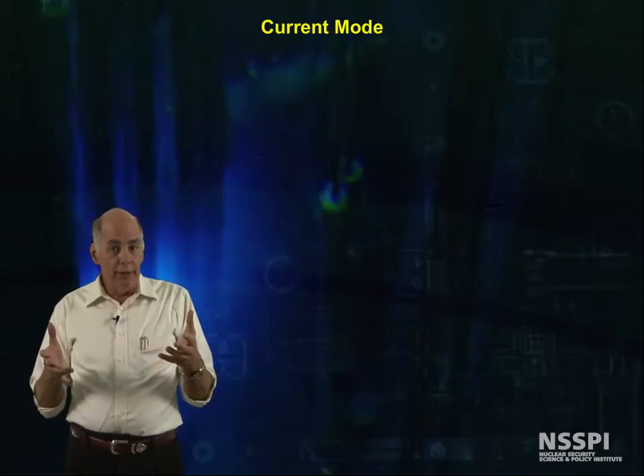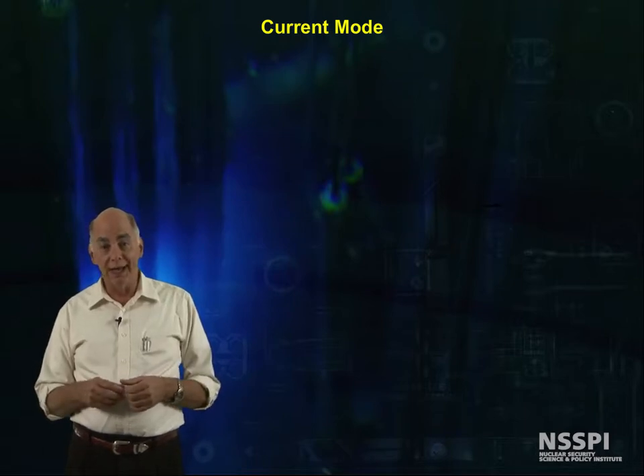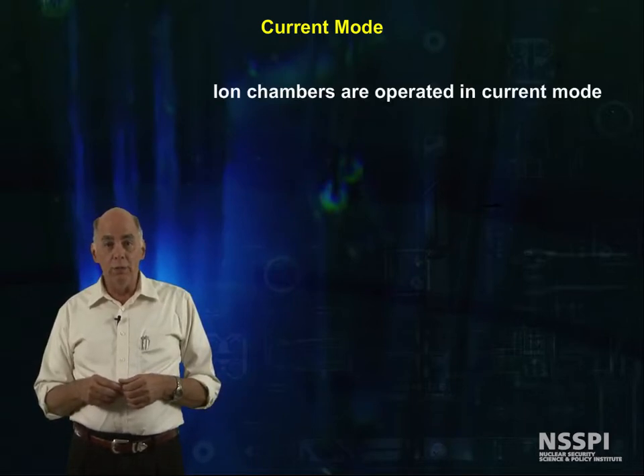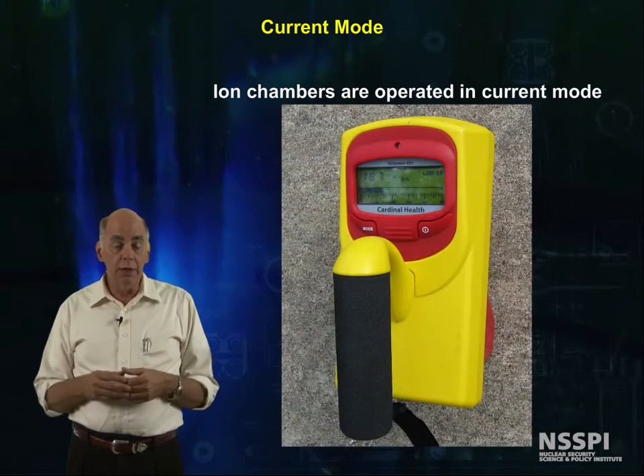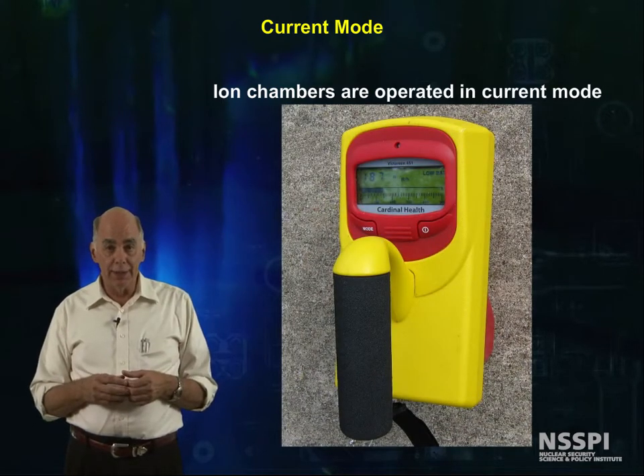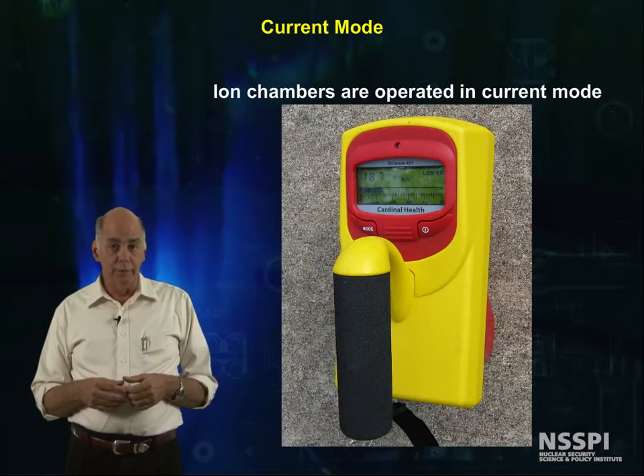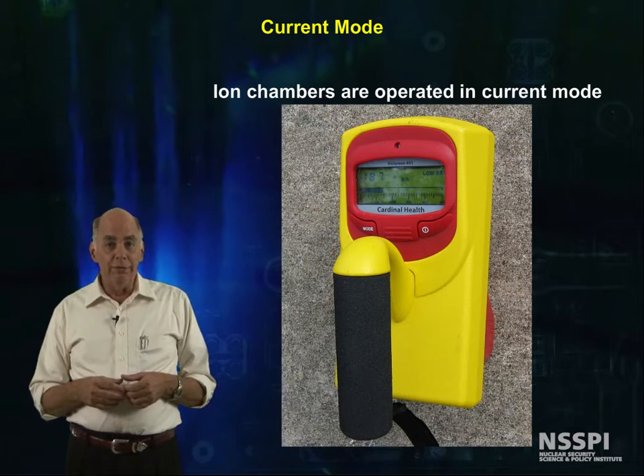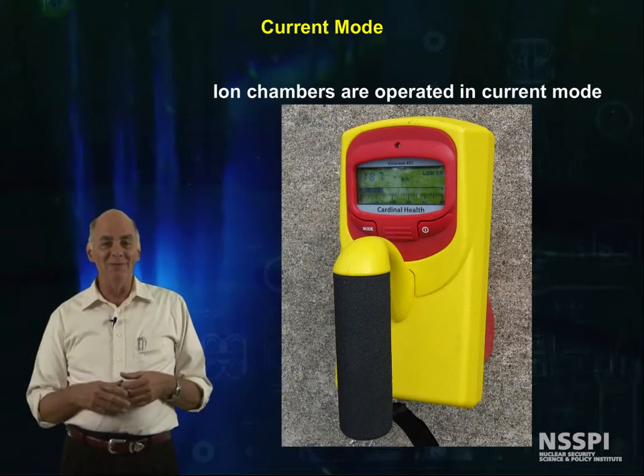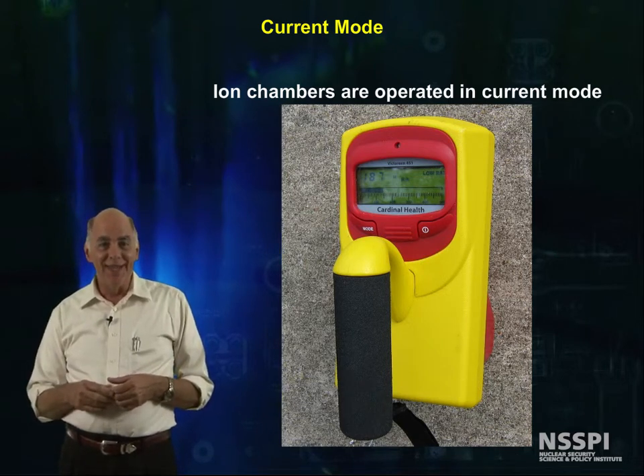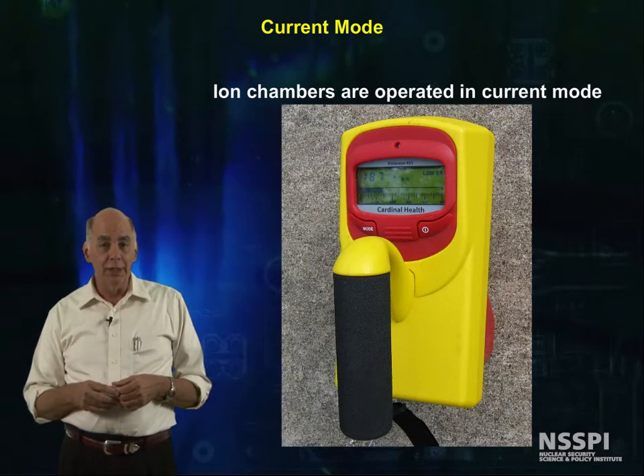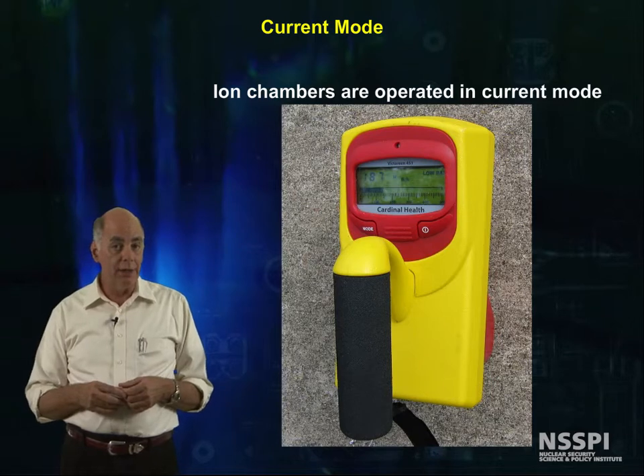Once you've got the charge separated, there are two ways to monitor the signal coming from the detector. One thing we can do is just measure the current itself produced by the ionization of the gas by the radiation. This strategy is used in ion chambers — the instruments that health physicists wave around in front of them when they measure dose is a gas-filled detector, and the current from the sensitive volume can be related fairly easily to dose.